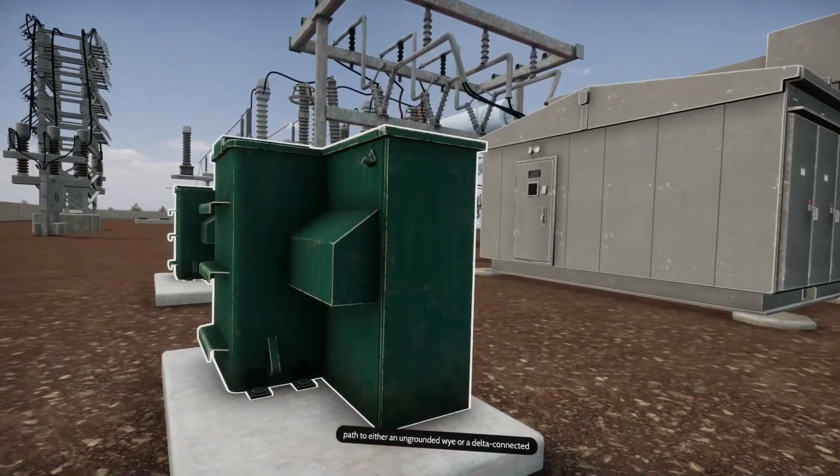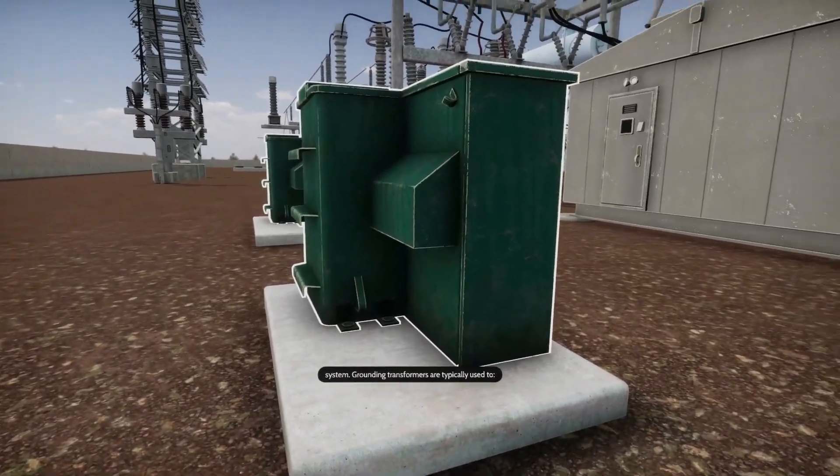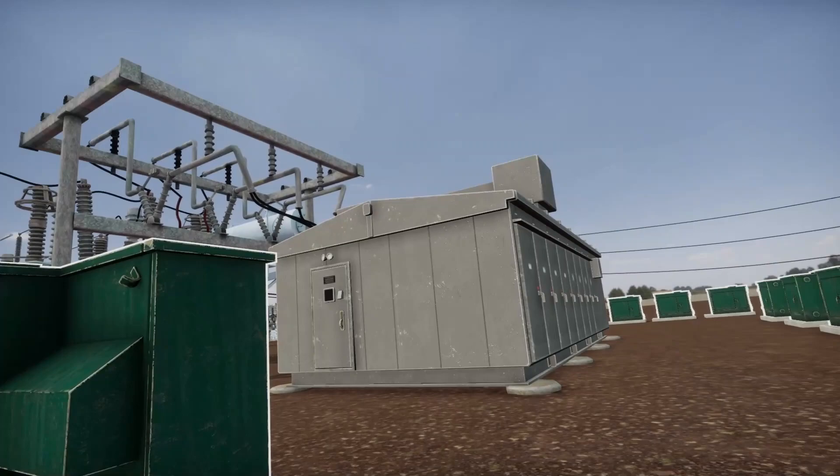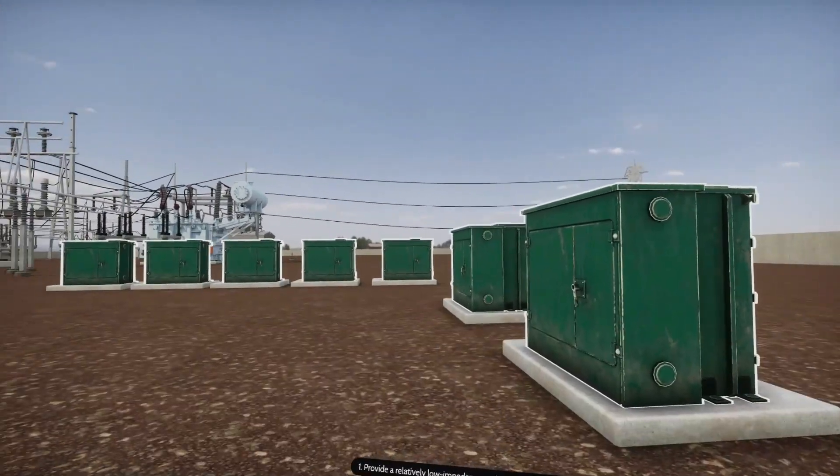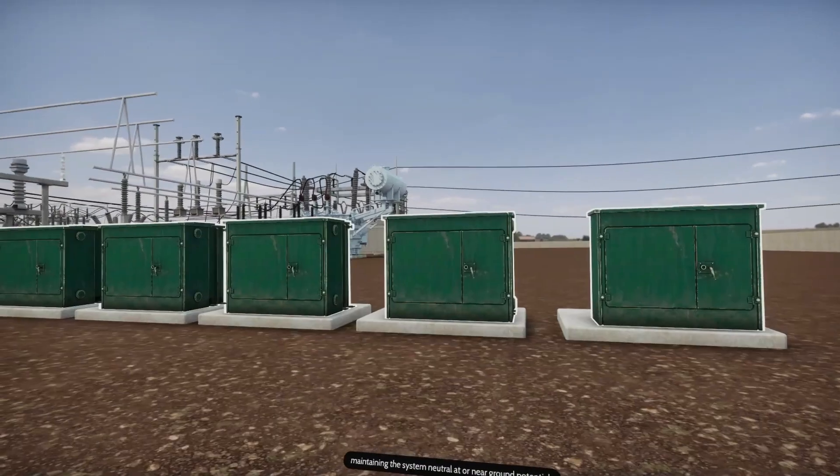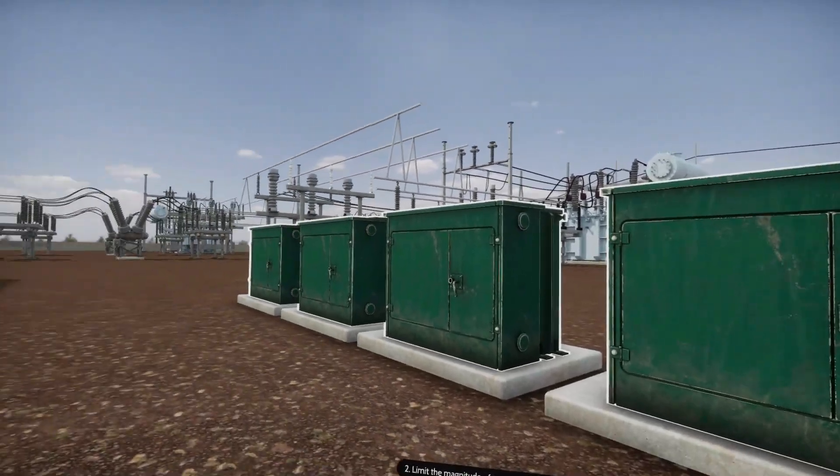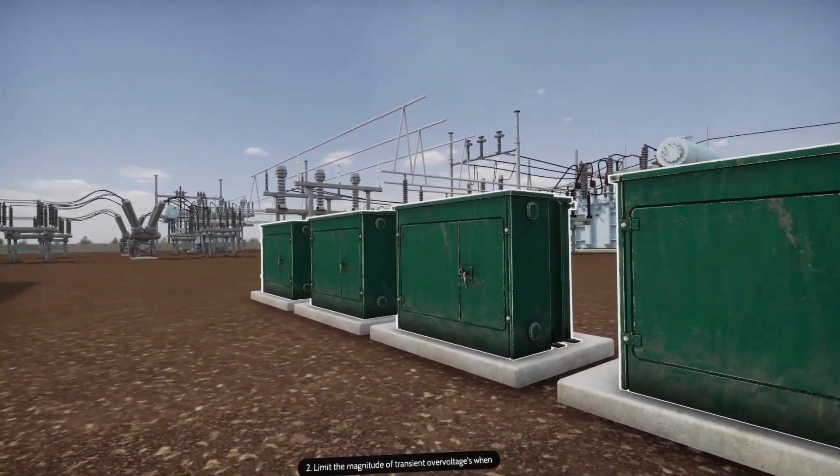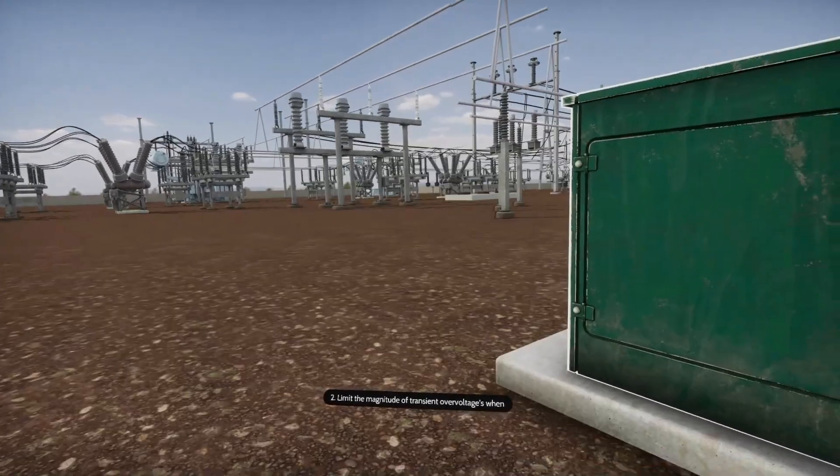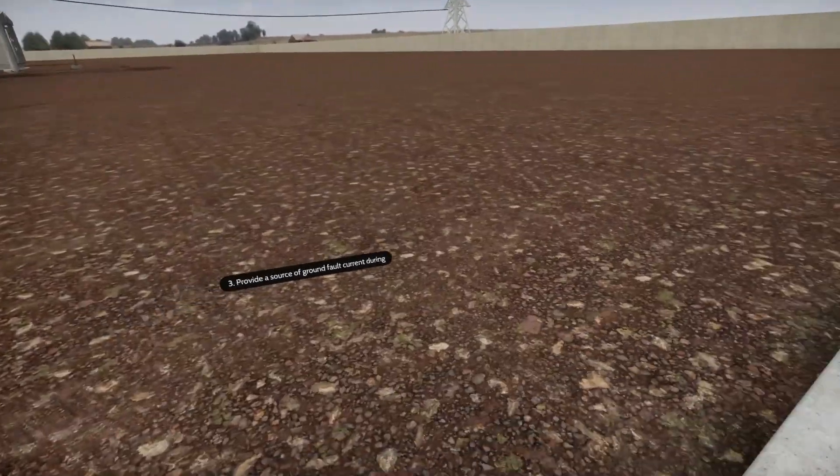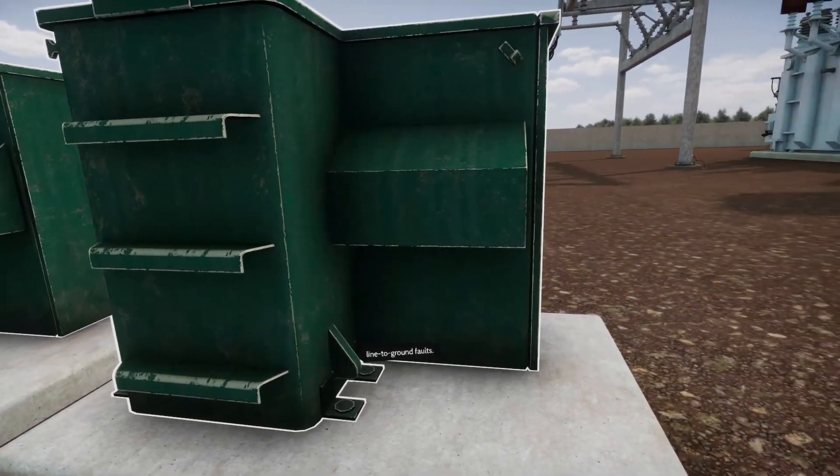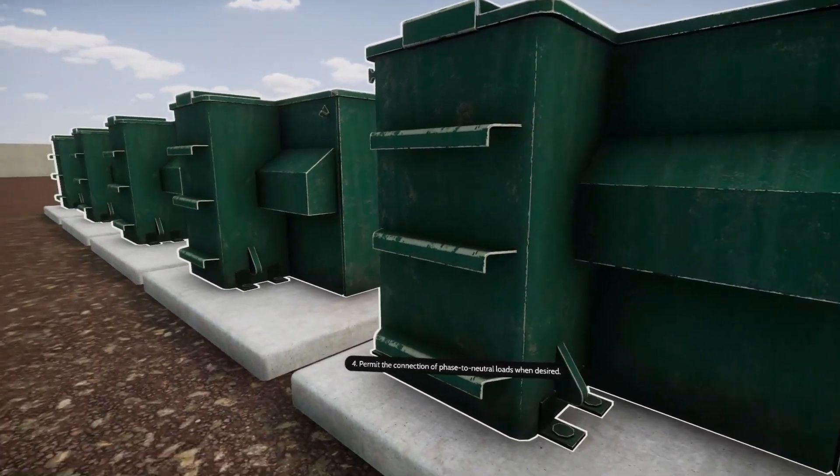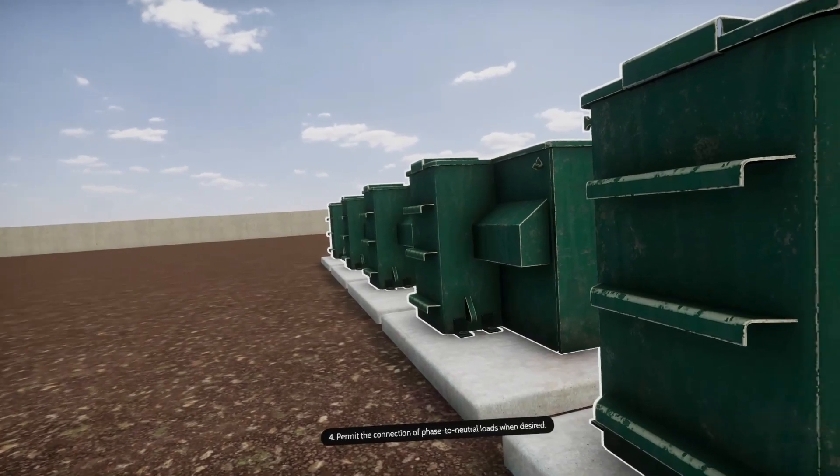Grounding transformers are typically used to: 1. Provide a relatively low impedance path to ground, thereby maintaining the system neutral at or near ground potential. 2. Limit the magnitude of transient over-voltages when re-striking ground faults occur. 3. Provide a source of ground fault current during line to ground faults. 4. Permit the connection of phase to neutral loads when desired.